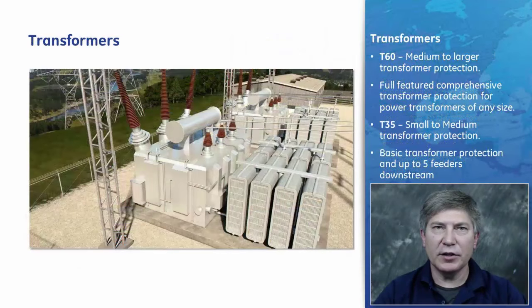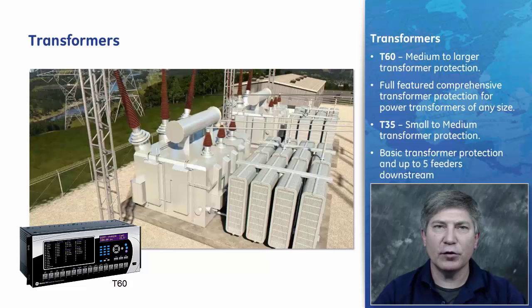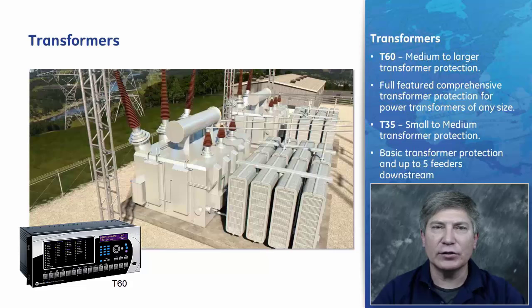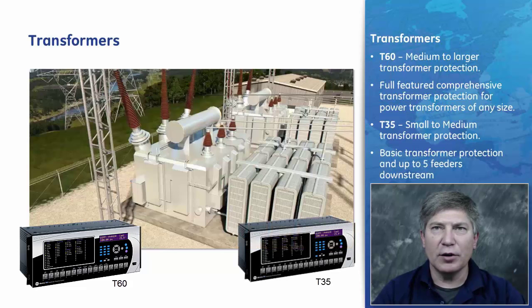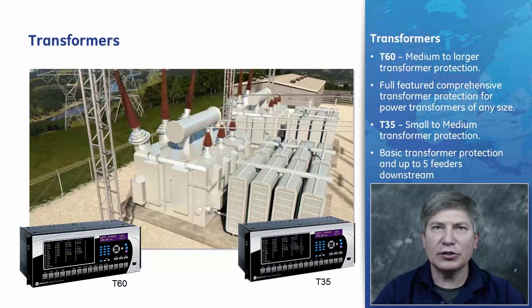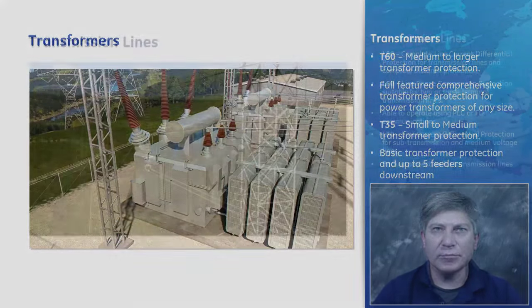Under transformers, we have the T60 for medium to large transformers. It provides automatic or user-definable magnitude reference winding selection for CT ratio matching and performs automatic phase shift compensation for all types of transformer winding connections. The T35 is basic transformer protection, capable of protecting combined main power transformers and up to five feeders downstream. The T35 provides automatic and user-definable magnitude reference winding selection for CT ratio matching, automatic phase shift compensation, and allows users to enable removal of zero sequence current for delta connection transformer windings.